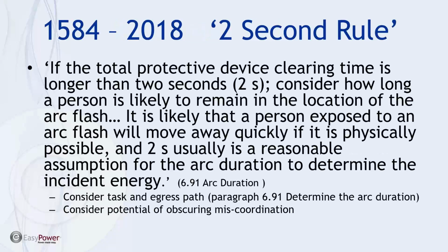Now, I put the 2-second rule designation in quotes because in the original 2002 version, the discussion about a 2-second time limit was in an annex and not technically part of the standard. They refer to those as informational annexes, and there's a lot of information even in today's release. But it now states in the body of the standard, in section 6.9.1, discussion of arc duration.